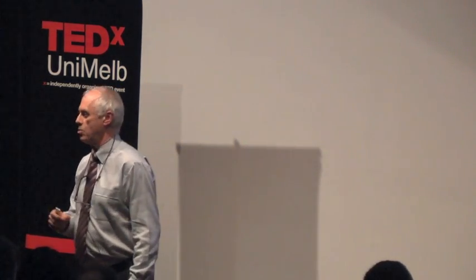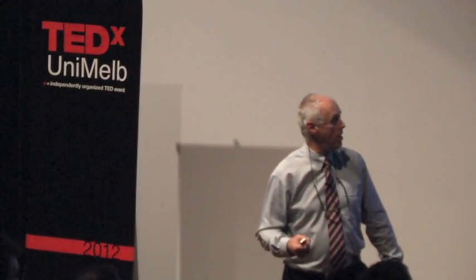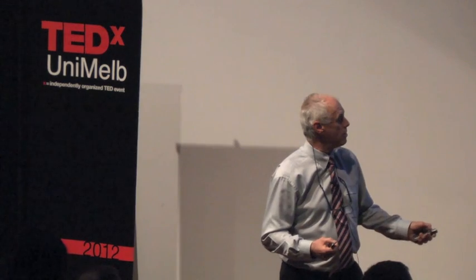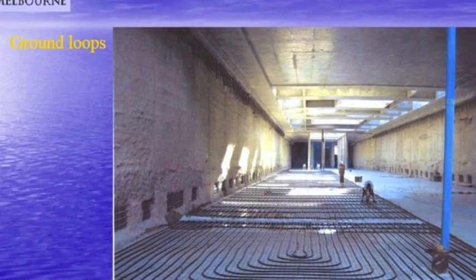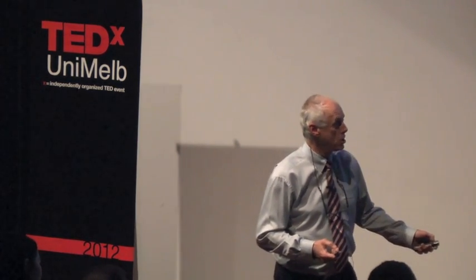For domestic-style applications, when you're going into the ground with foundations, make use of the holes you're already digging. This is how I got into it - I'm a geotechnical engineer, and I spent thirty years designing these things. This is the reinforcing cage for a large bored pile, about a metre and a half in diameter. It goes down the borehole and concrete is poured. If you've got a hole in the ground, why not put some pipes in there as well, at very little extra cost? These are vertical holes, and just as you have vertical ones, you can have horizontal ones in large commercial foundations. This is an underground station in Vienna - why not put all this piping in the platform area, cover it with concrete, and use it as a heating and cooling source for buildings above?